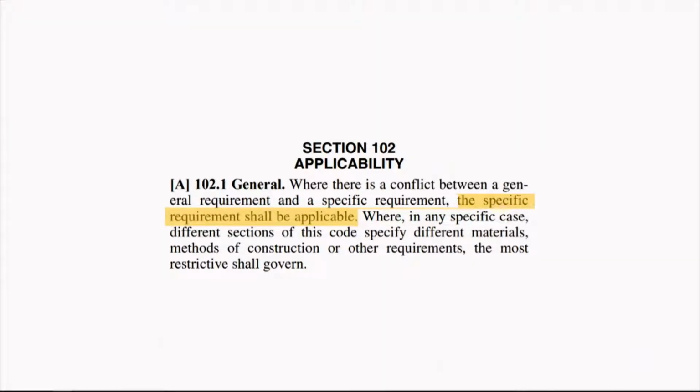They assert that because the separation requirements of 406.3.1 are not specified, they are subject to interpretation. While we agree that the separation requirements of 406.3.1 are general in their definition, those found in the following section, 406.3.2, titled Separation, are not. And again, Chapter 1 directs us to look at the more specific requirements when compared to more general ones.